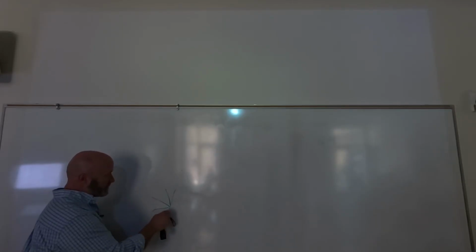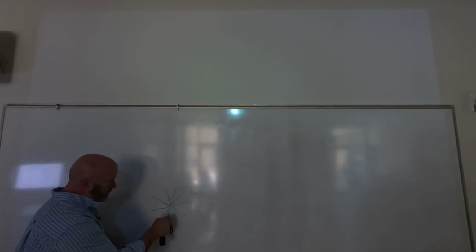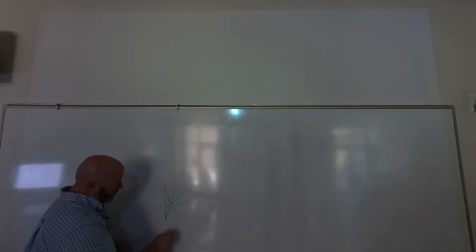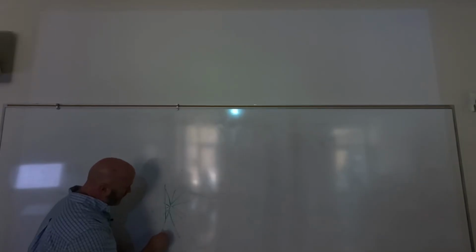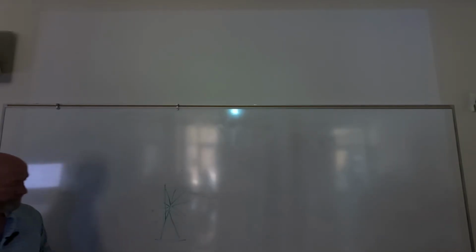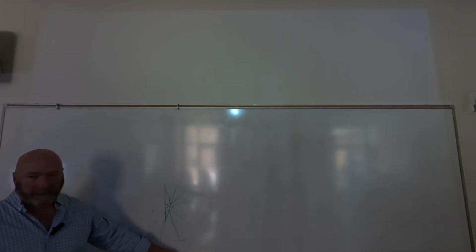It's very important that you understand, we're going to get into it later in the semester, but we don't focus the X-ray beam. We can't focus the X-ray beam. The X-ray beam diverges, and at the point of impact on the anode, X-rays go off in all directions with equal intensity, and we call that isotropic emissions. This is the backside of the anode, so those are absorbed inside of the anode. What we want to do is limit the beam to what comes through the window, and then we further limit that beam in our collimator housing down here.